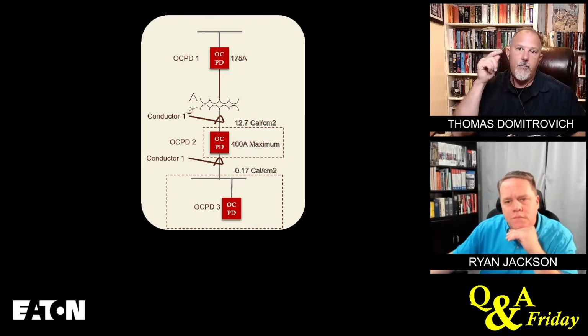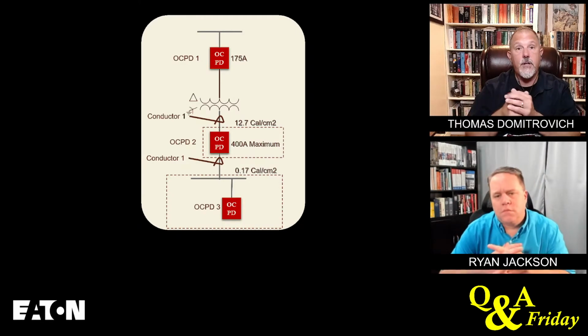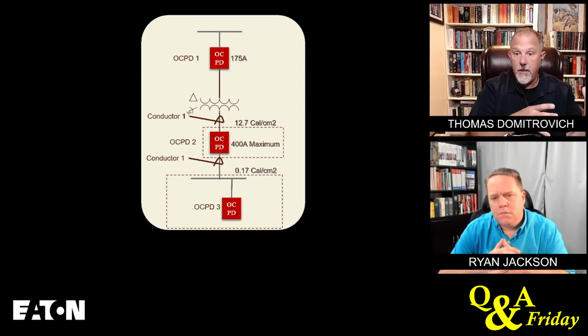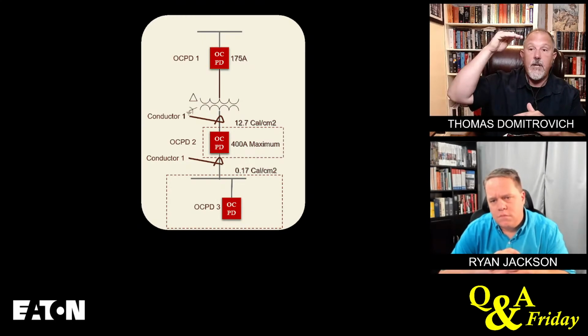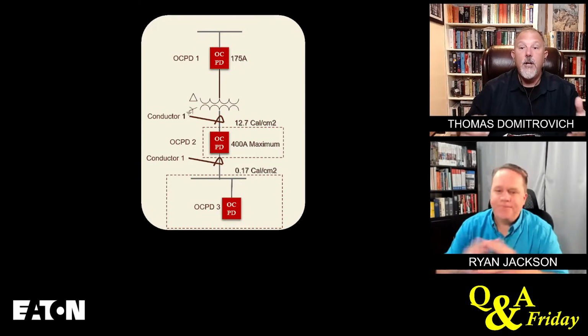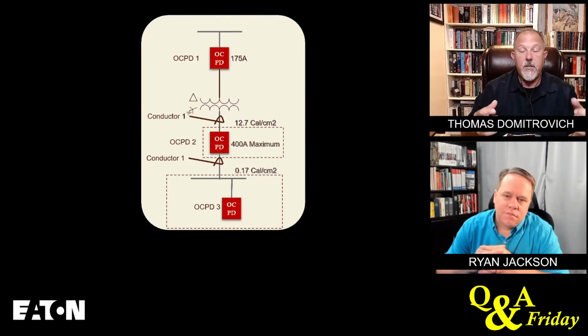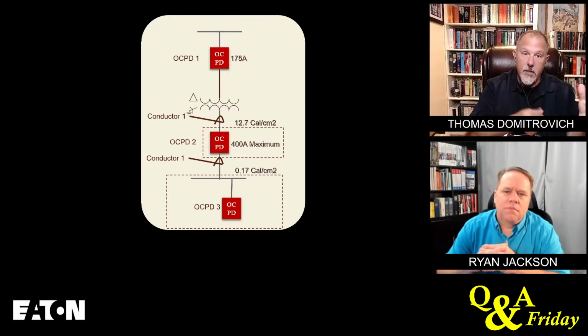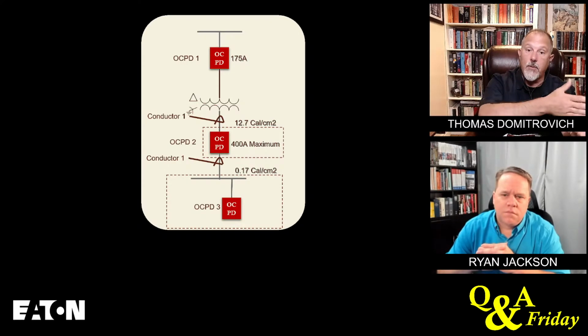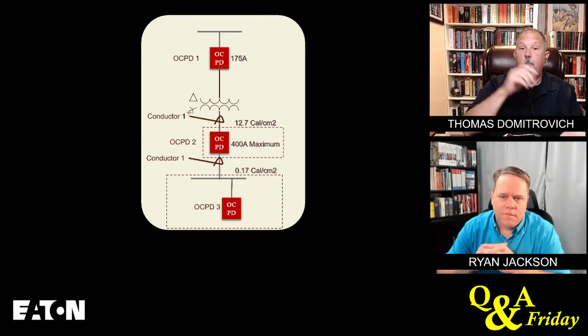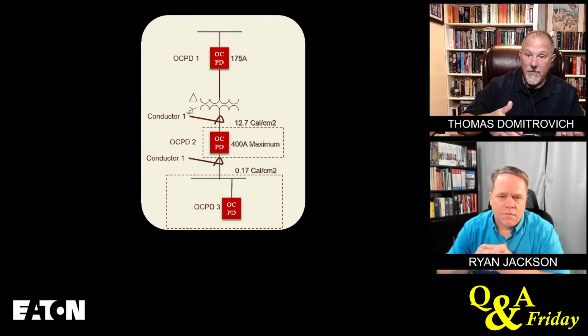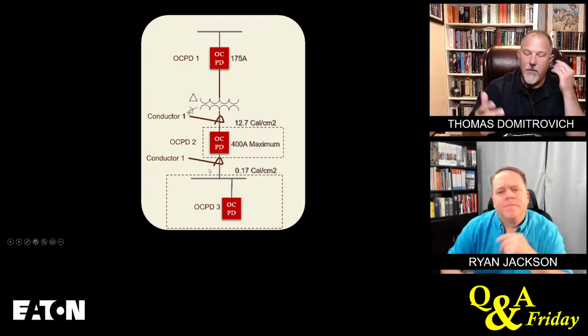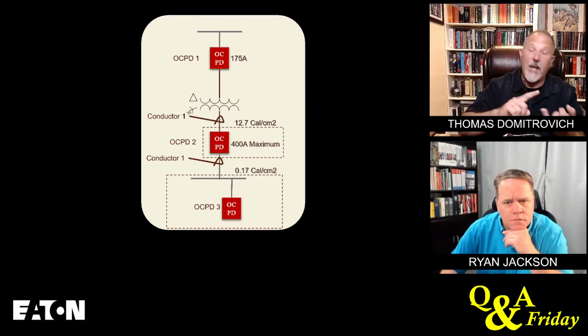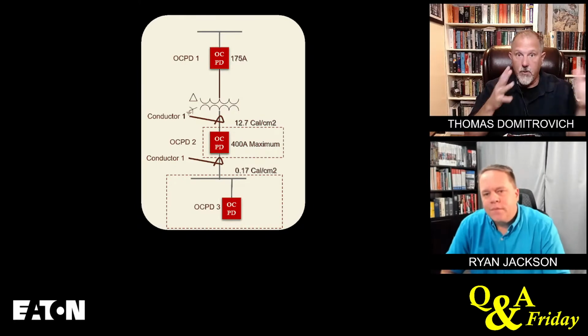The reason they did the arc reduction maintenance switch was because if it's a piece of equipment like machinery, the likelihood of doing justified energized work is high because you're troubleshooting. So the philosophy of the plant manager was to put these breakers in a box with an arc reduction maintenance switch so that when justified energized work was done, the incident energy was low. But it also provides the ability to turn it off right there. I talked to him about this, and his complaint was not just expense, but space. You need to find the room to do that on the wall.